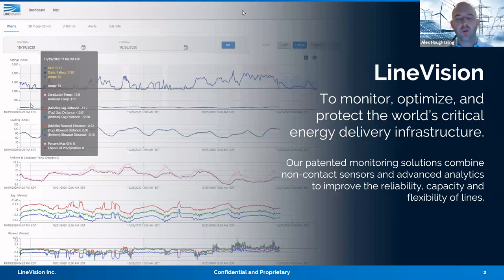We're going to discuss line ratings for 2021 and beyond, but no issue exists in isolation. LineVision doesn't monitor conductors just because utilities want better information. We do it because utilities face never-before-seen problems. The growth of renewables is relentless, and as a country we face $8 billion a year in congestion costs. 50% of the conductors hanging from your towers are at or near the end of their useful life, and we've already seen the first utility bankruptcy from wildfire and climate risk.